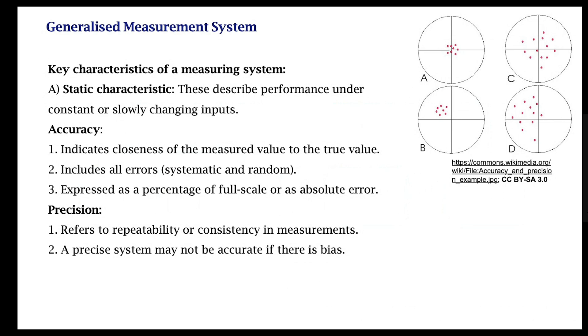If I know the systematic error, I also know ways through which I can remove it, because it's systematic and I can account for it. Accuracy is usually expressed as a percentage of the full scale value. For example, if I'm measuring 100 units and the system is 10% accurate, and the reading is 30, the actual value can be on either side of 30 by 10 percent.